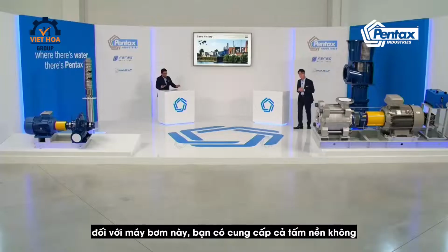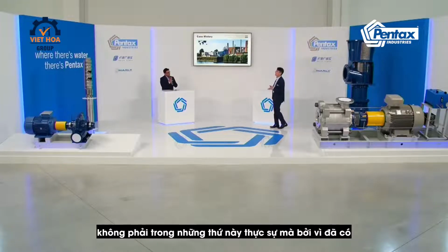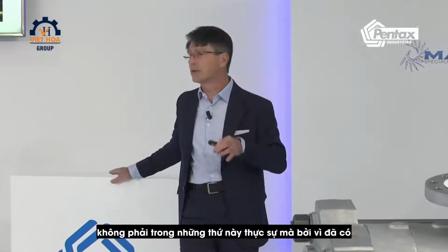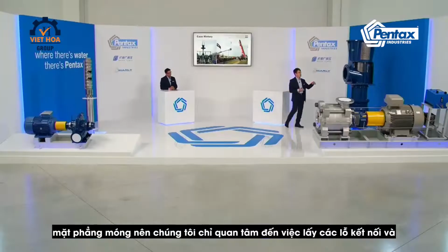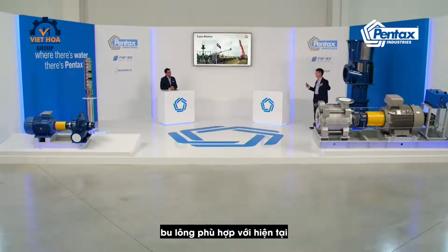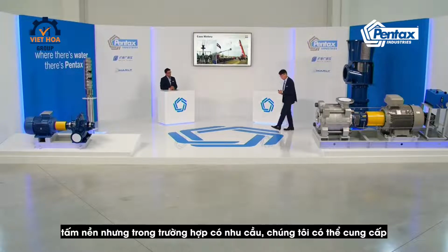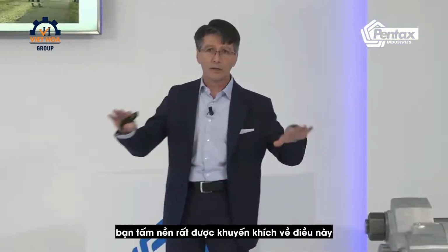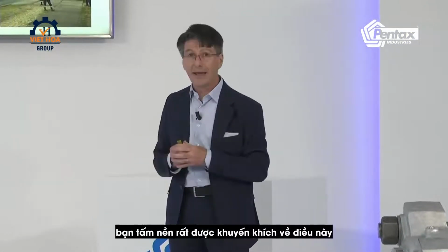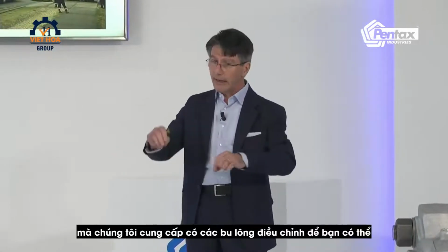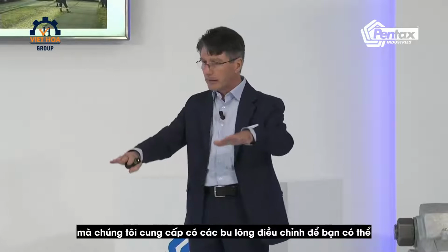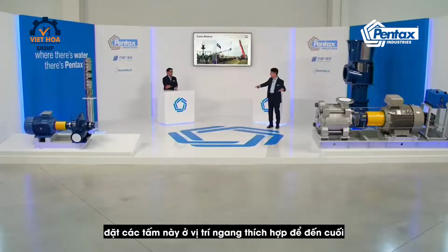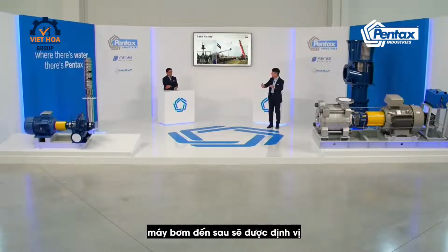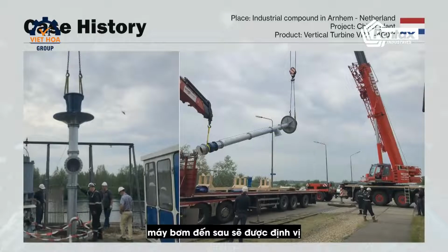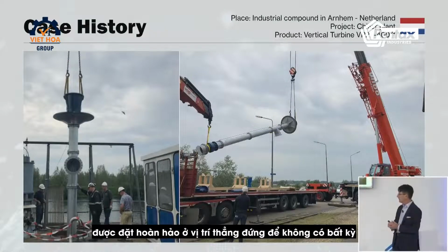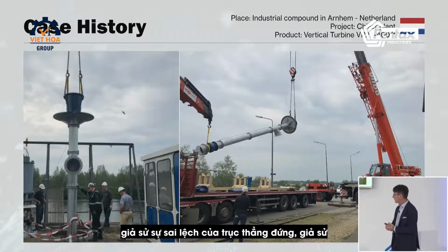For this pump, do you supply even the foundation plate? Not in this, actually, because there was the existing foundation plate, so we just care to get the connection holes and bolts to be suitable for the existing foundation plate. But in case of needs, yes, we can provide you the foundation plates, which is very recommended on this application because the foundation plates that we provide has adjusting bolts in order that you can put on the proper horizontal position these plates in order that the pump that is coming after will be placed perfectly in the vertical position, so not to have any misalignment of the vertical shaft.